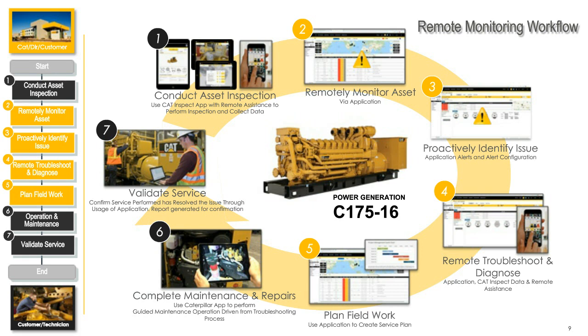Yeah, I guess the starting point, increasingly there's a view to manage the obsolescence of technology, starting with the control systems. We've got controls, or gensets, that have been out there for 30, 40 years. Even with a standby genset, the genset might not be running, but your controller's on all the time, so you should ask, should you be doing some controls upgrades?